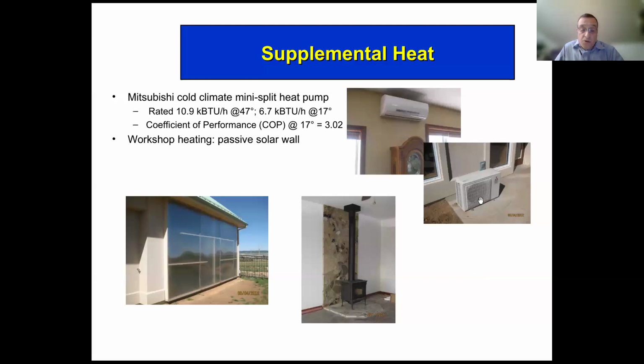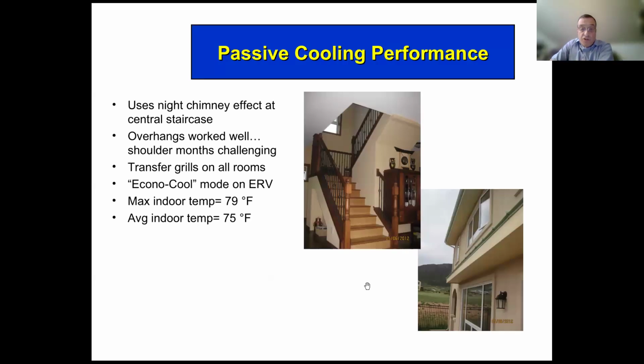So that is the sole source of mechanical heat for the house. You say, well, how does a point source on the first floor heat the whole house? Well, we put transfer grills between all the rooms, so all of the bedrooms and bathrooms are connected through transfer grills. And also the ventilation system moves air through the house. And if you have a tight enough shell, you don't get isolated cold spots. And so you get fairly even heating, within a couple of degrees throughout the whole house, with just a single point source heater. And we do also have a wood burning, high performance wood burning stove.